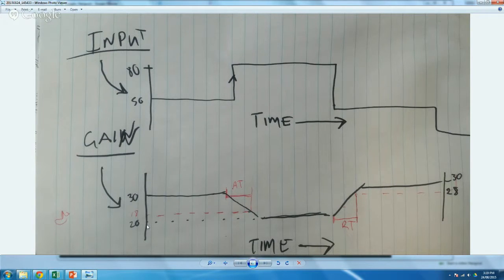The gain has corresponding changes because it's a compression hearing aid that's listening to this input. The gain for a 50 dB input is 30 dB, and that goes along, but there's that change in the signal input, and the input goes up to 80. Because of that, the hearing aid goes into compression, but it takes some time to do so.